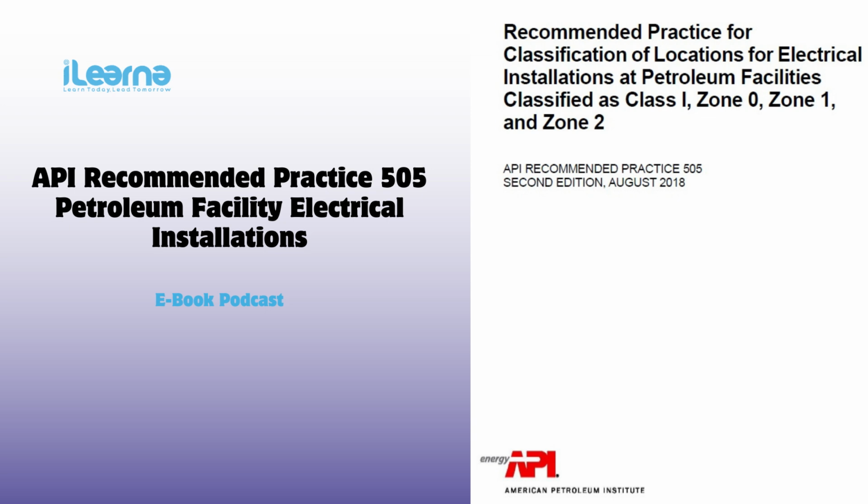What exactly does API 505 cover, and what does it leave out? Okay, so this is super important. API 505 is only about flammable gases and liquids. Things like gasoline or propane. If you're dealing with something else that's hazardous, like combustible dust or ignitable fibers, you'll need to consult a different standard altogether. So no mixing and matching hazards. Flammable gases and liquids only.